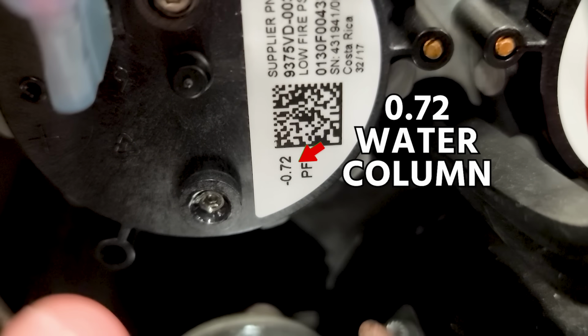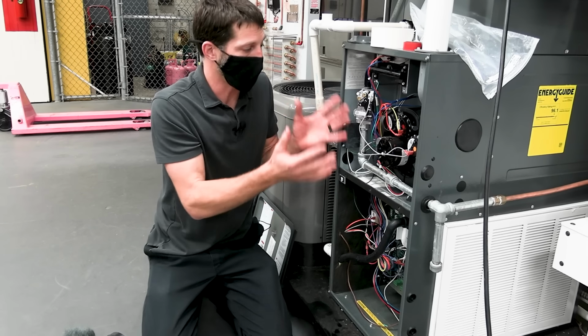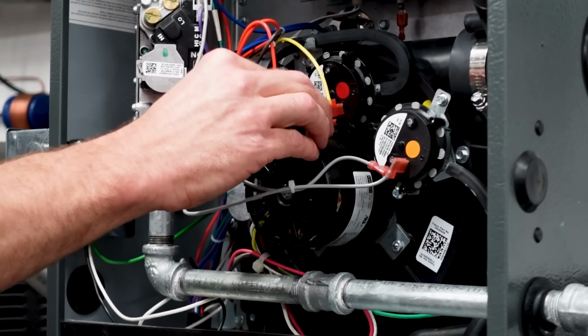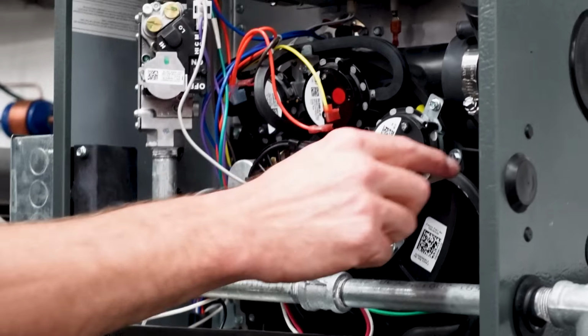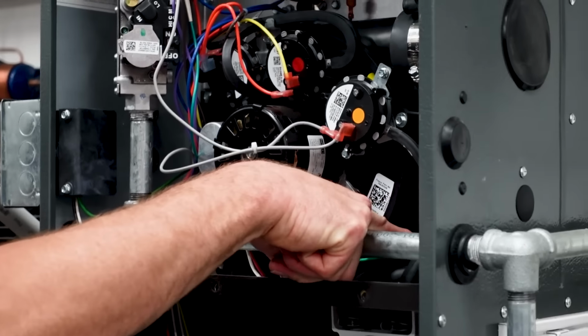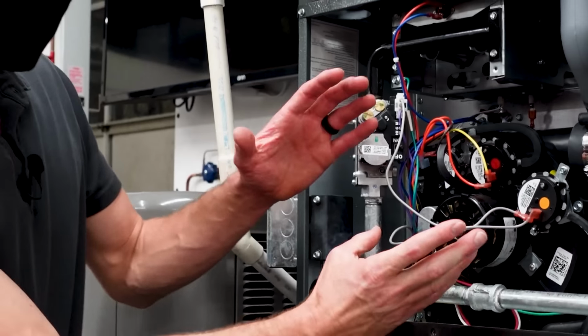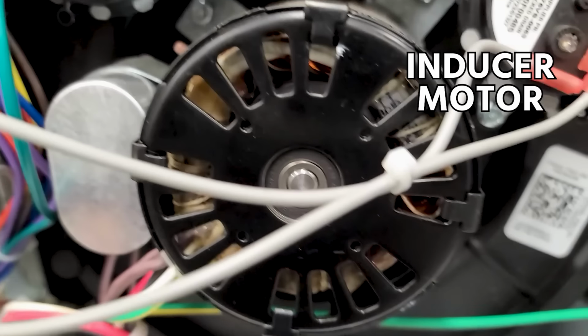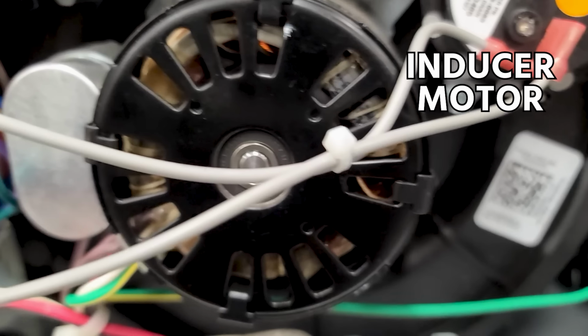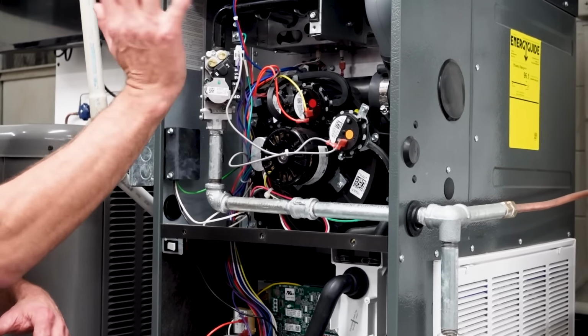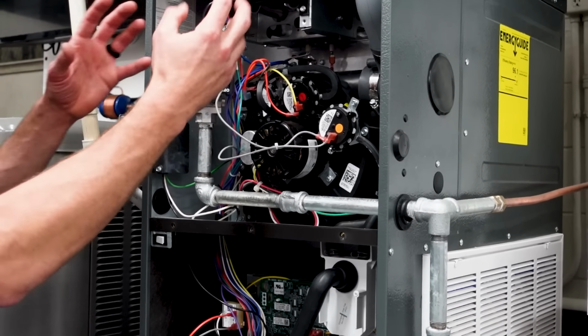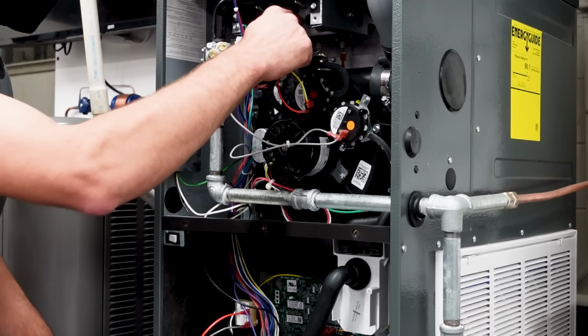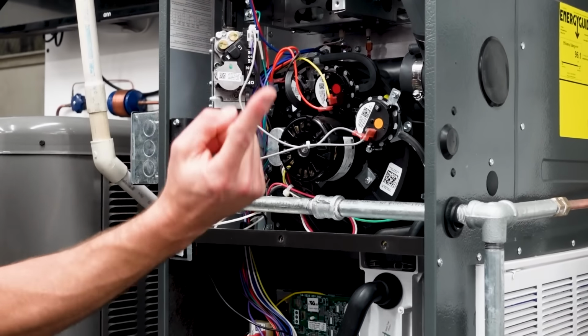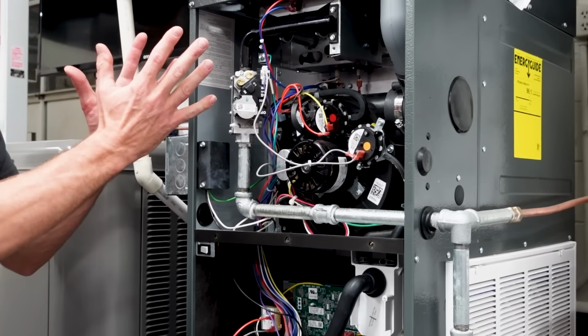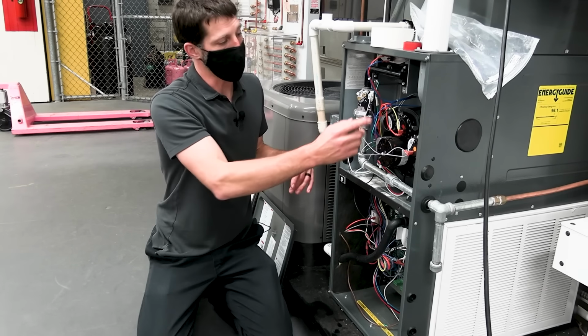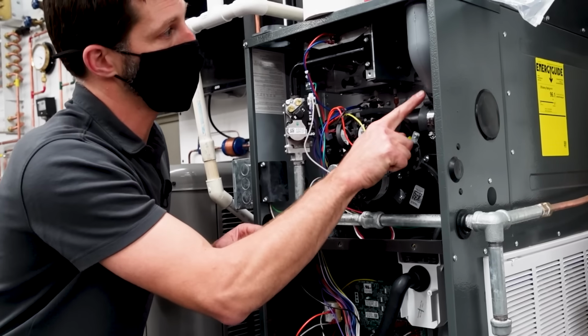Well, what that's doing is measuring the negative water column pressure of the inducer motor while the inducer motor is running. This one right here has a tube going down into the collector box that's behind the inducer motor. So this is the inducer motor, and its job is to pull the combustion air from out here into this area, mix with the gas, and it's pulling the exhaust through the whole heat exchanger, through the primary and the secondary heat exchanger, and then it's coming into the inducer motor and pushing out this way.